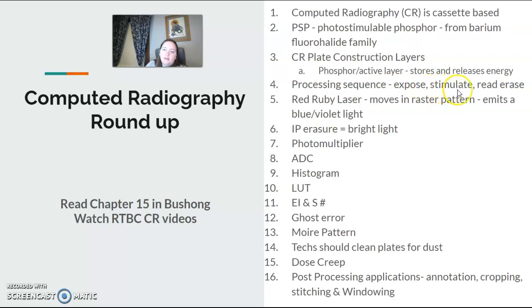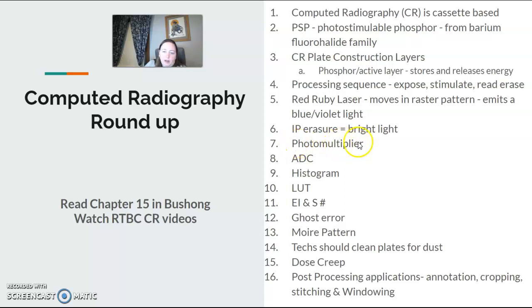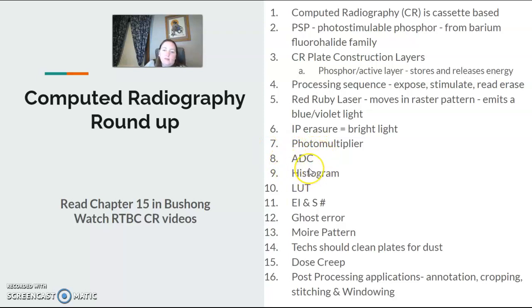The processing sequence: it's exposed, it's stimulated, it's read, it's erased. The red ruby laser — it's not really a ruby, it's just a red laser — moves in a raster pattern, left to right down the cassette, which emits that blue or violet light. It's erased by a bright light. The photo multiplier and analog-to-digital converter then come into play. The photo multiplier takes the light photons, and the analog-to-digital converter takes that electrical signal and converts it to a digital readout that we can see on the monitor.